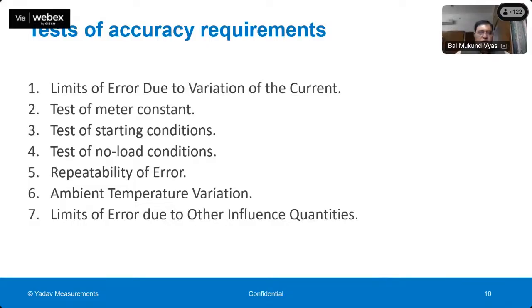Okay. So now let us talk about what are the accuracy tests which the meter has to undergo before it is certified, whether as per the OIML standard or the Indian standard or the IEC standard, depending on which country we are working in or where the meter is. But all these requirements are almost similar in all these standards. There might be slight differences in the limits, and slight differences in the test methods, but more or less they are similar. So of course the meter has to undergo the limits of error due to variation of the current. So at different currents when the meter is connected, the load might be very small. Sometimes it may be full load, it may be 50% load, it may be 5% load, or sometimes there is no load. So the accuracy of the meter has to be tested under all these conditions.